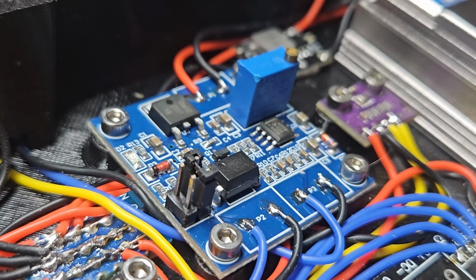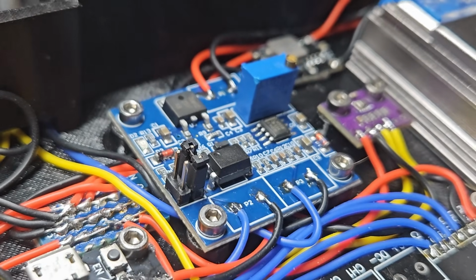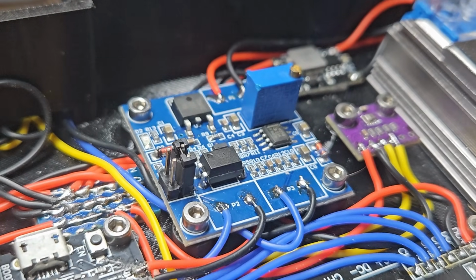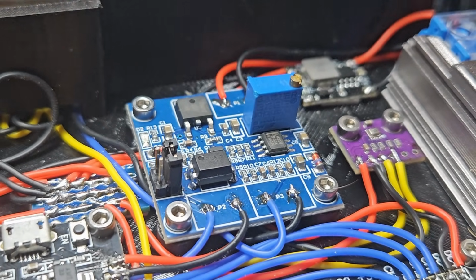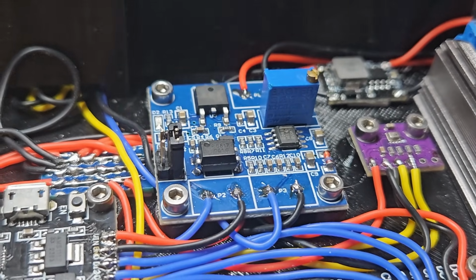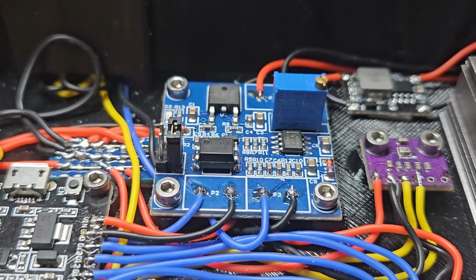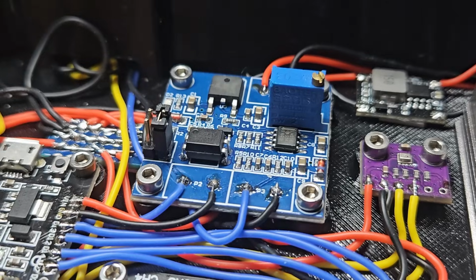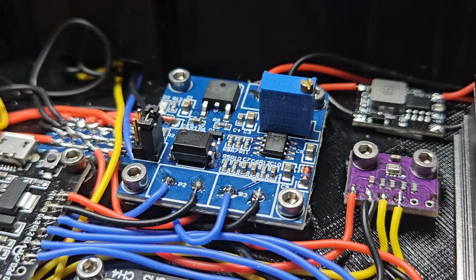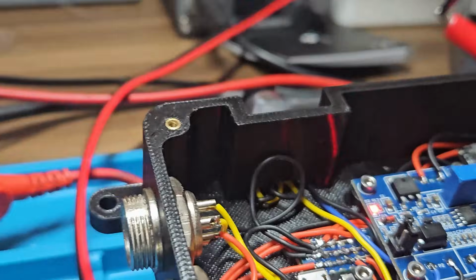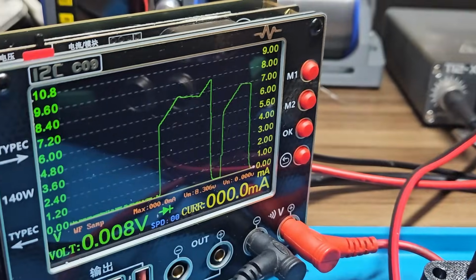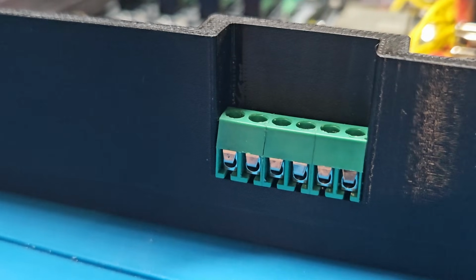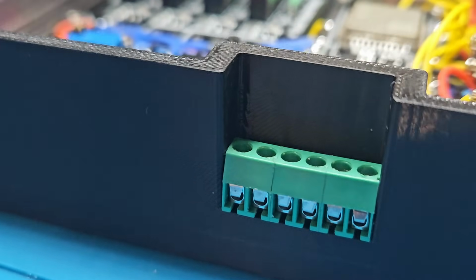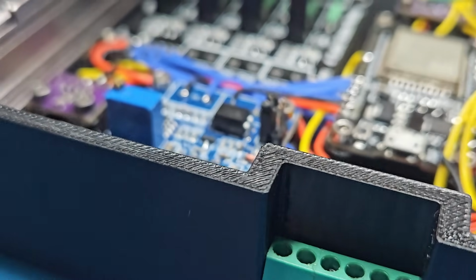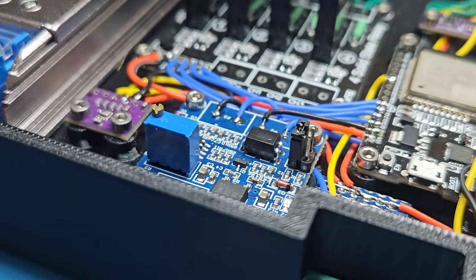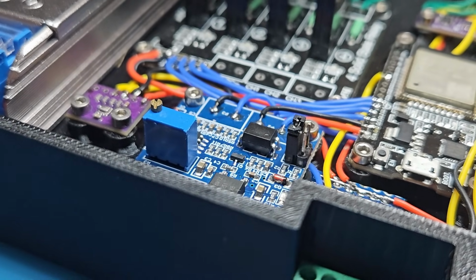The second output module is the 0 to 10 volts converter. As the name suggests, on its output you get a 0 to 10 volts analog signal. On the input it takes the PWM signal from the ESP and converts it to that signal. It's used to drive the VFD, as devices like this usually take this kind of signal to set the desired drive speed. This module is powered with 12 volts, because any lower voltage would not be enough to produce a 0 to 10 volts signal.